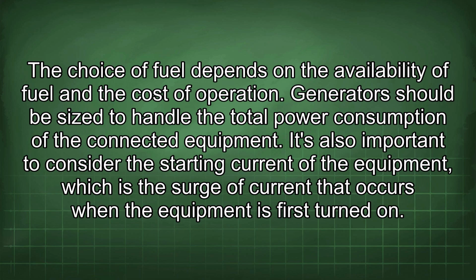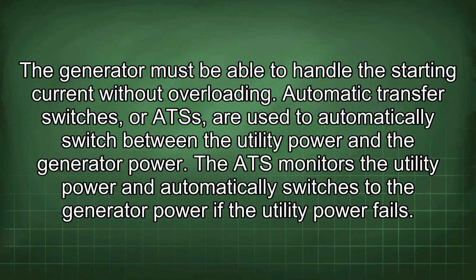It's also important to consider the starting current of the equipment, which is the surge of current that occurs when the equipment is first turned on. The generator must be able to handle the starting current without overloading. Automatic transfer switches, or ATSs, are used to automatically switch between the utility power and the generator power.